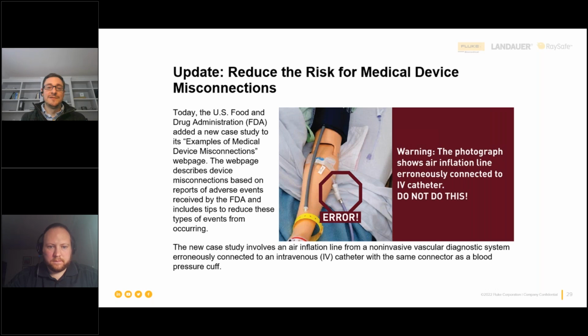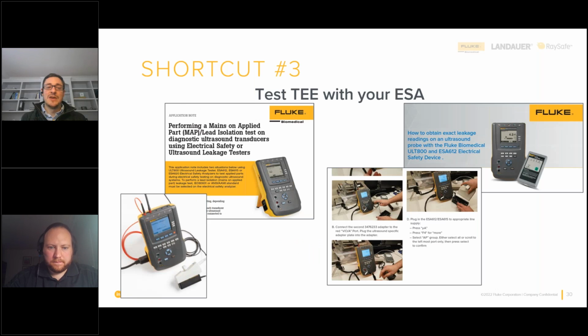But with that, I'm going to move on to the third shortcut. Many of you probably own a ULT 800 to do some TEE probe testing. But one thing you might not know is that you can actually use your Fluke Biomedical ESA to do similar testing. The ESA can be used along with, again, another part number here, 3476233, to test conductivity, and then the ULT adapter plates can actually be connected to the ESA as well. The added benefit here is, compared to the ULT 800, where you're going to get a pass-fail, with the ESA you can actually get the exact leakage readings.